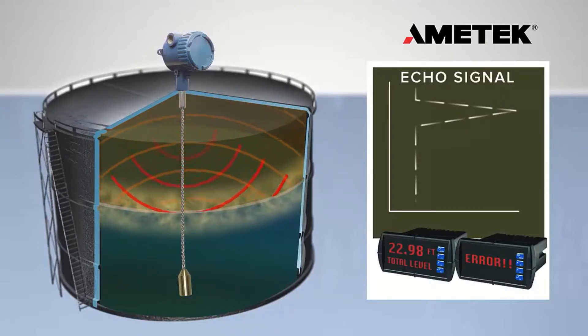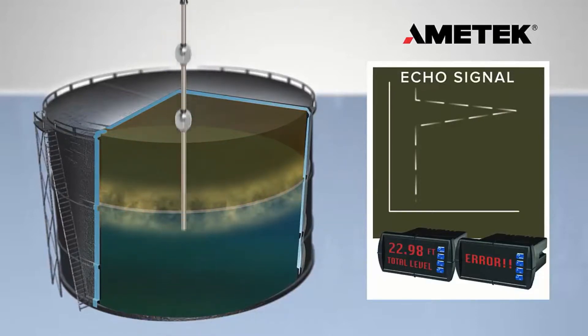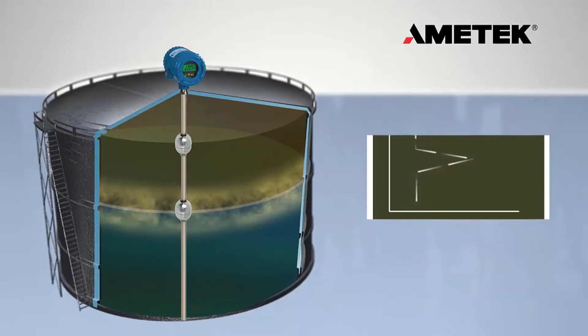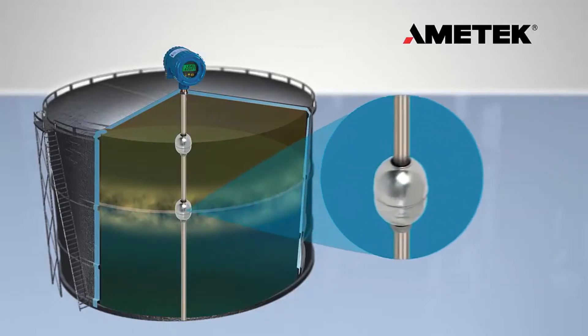If this occurs, it is extremely difficult to maintain control of the process. Using a float-based magnetostrictive technology, the measurement becomes straightforward. Both product and interface return signals are generated by the reflection of a magnetically induced strain on the measurement wire, which is embedded in the probe.